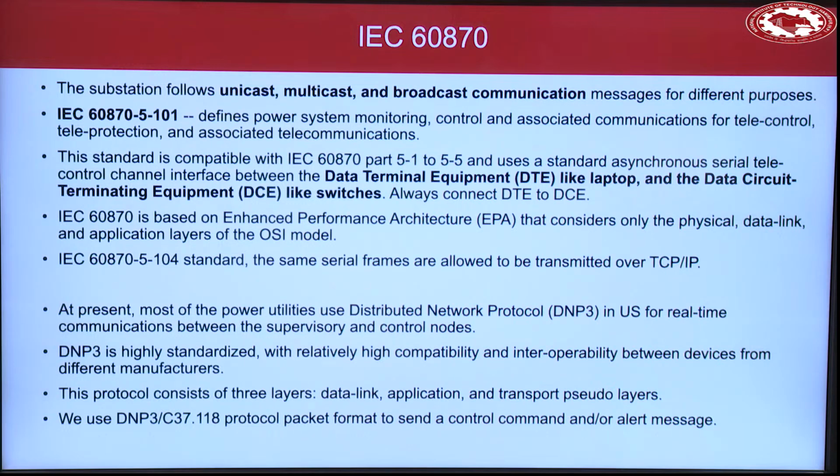So this particular protocol is based on the enhanced performance architecture that supports the physical, data link and application layers of the protocol, not everything else. But if you need to use TCP/IP, you can have the same serial frame to use it. This protocol also supports DNP3, which is the distributed network protocol, since the standard supports it. In the US, we've seen how it looks. If you are in a European country, we do use the Modbus protocol most of the time. And if you are in America, in the US, they do use the distributed network protocol. Again, there were several vulnerabilities in DNP3. They came up with an improved version of DNP3 that has some level of security in it, which is a good practice.